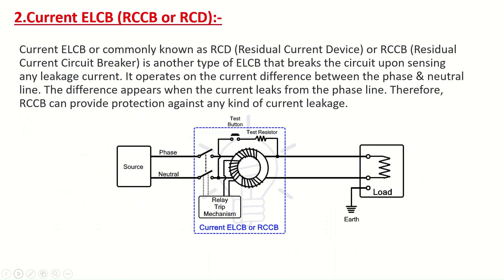Current ELCB — RCCB or RCD. Current ELCB, commonly known as RCD (Residual Current Device) or RCCB (Residual Current Circuit Breaker), is another type of ELCB that breaks the circuit upon sensing any leakage current. It operates on the current difference between the phase and neutral line. The difference appears when current leaks from the phase line, so RCCB can provide protection against any kind of current leakage.